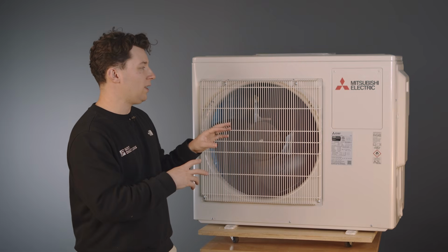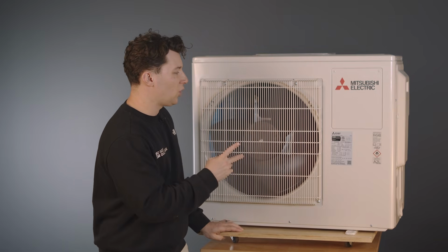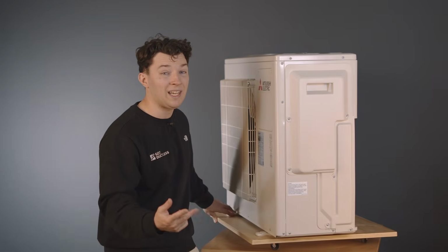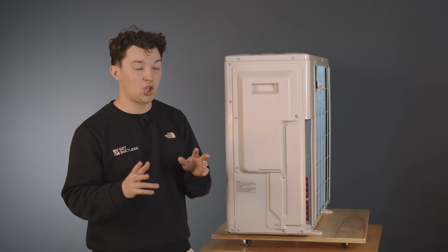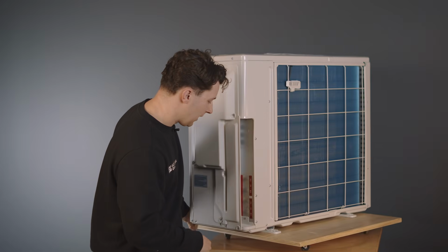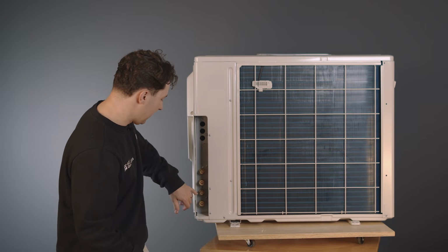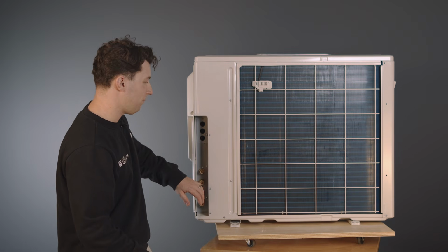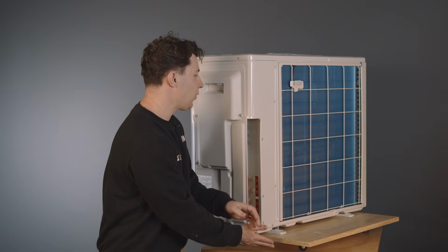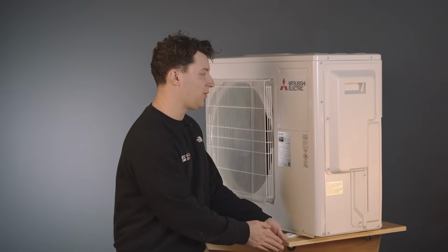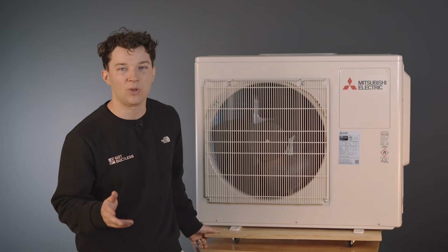But for this individual outdoor unit, the two-zone system, you can't just have one indoor unit connected to it. You have to have two indoor units connected to it here. And so here on the back side, you can see that there's port A and port B. And so you have to have two connected to it at the same time. You can't just install one indoor unit now and then another indoor unit later. On multi-zones, there's always the regulation that you have to have at least two indoor units connected to one multi-zone unit at any given time.